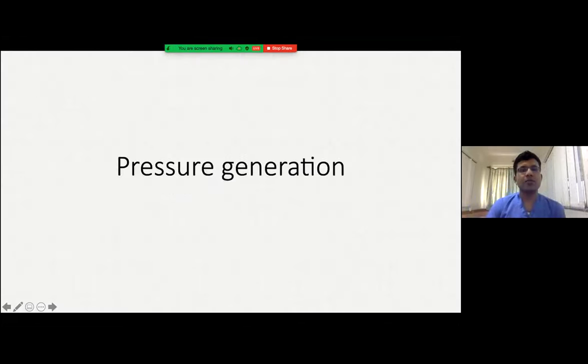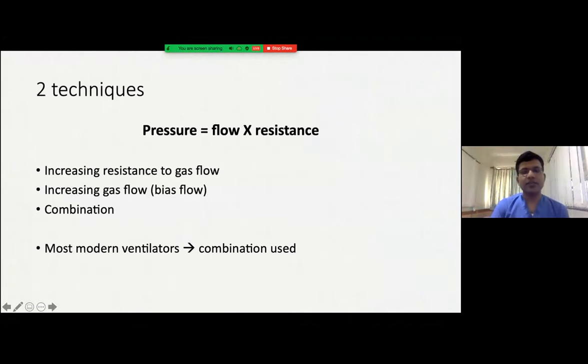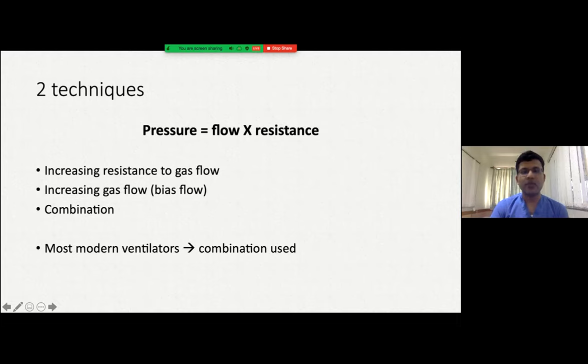I will now discuss pressure generation. There are two techniques by which pressure is generated. The physics formula is: Pressure is the product of flow and resistance. So either by increasing gas flow or by increasing resistance to gas flow, we can increase pressure. For most modern ventilators, they use a combination of both — increasing flow and also increasing resistance to increase pressure.